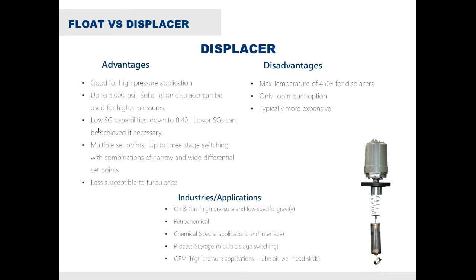Another advantage is low SG capabilities. With that spring, you can fine-tune the force balance equation and achieve low SGs — downwards of 0.4 SG, which is pretty low — and even lower than that if necessary. With displacers, you can also achieve multiple set points: up to three different set points, even with multiple displacers all sensing three different points inside the chamber or tank.